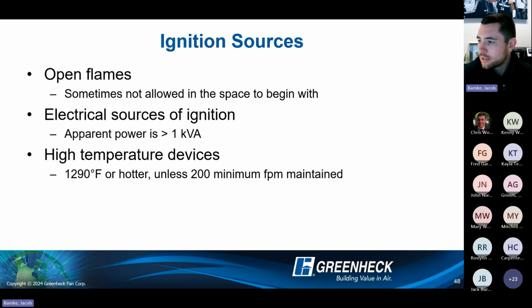And then on a variable volume system, will the unit maintain the minimum CFM, or will this need to be part of a control sequence? For all of our products, we will have a minimum, based on the housing size and the tonnage, a minimum fan speed that the unit is controlling to. So that will be communicated out. We're still finalizing some of our designs. If we go back one slide, oh, sorry, no, right here. There's certain feet per minute that we have to maintain in all these products.